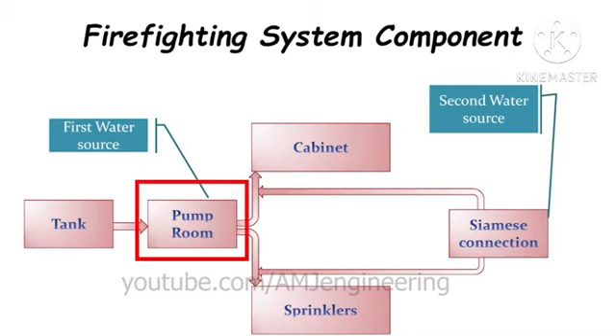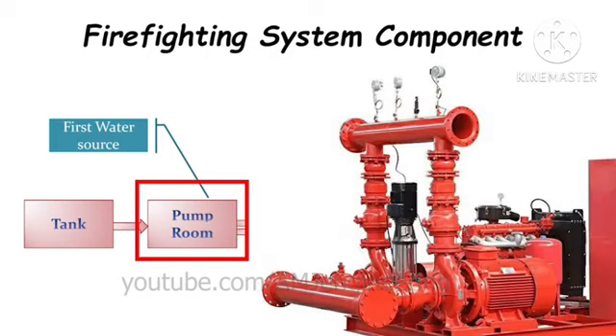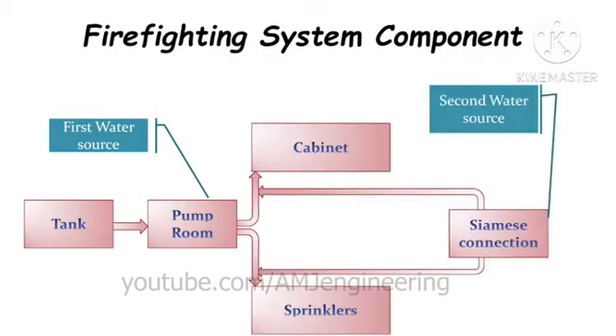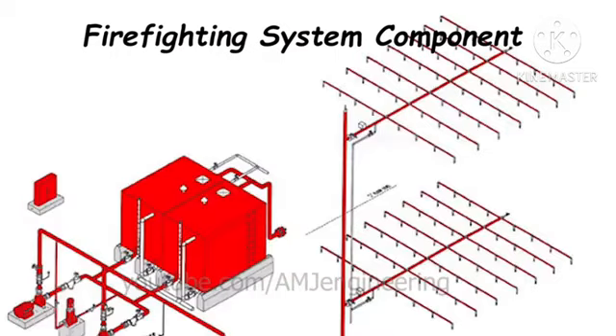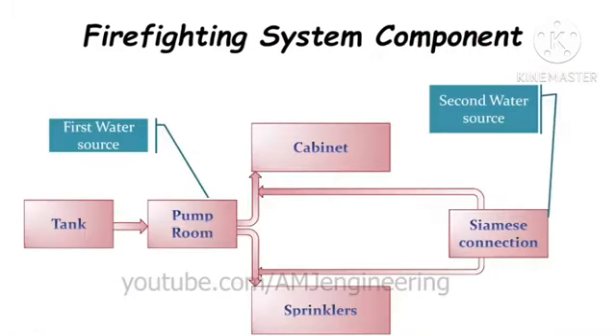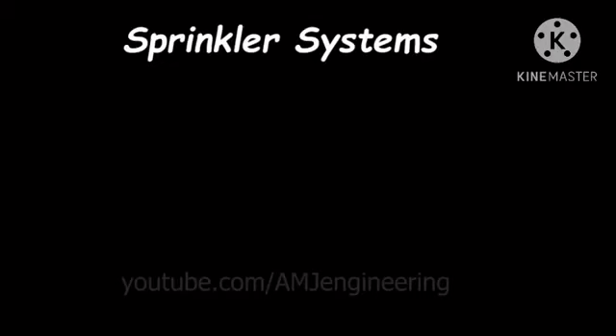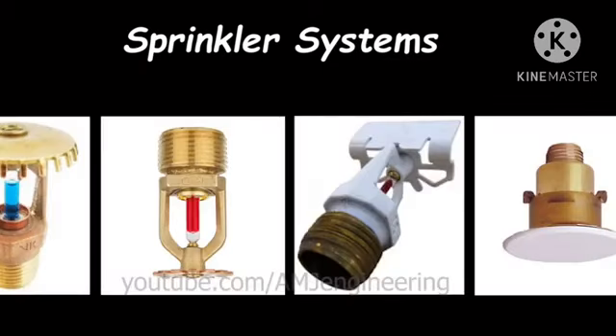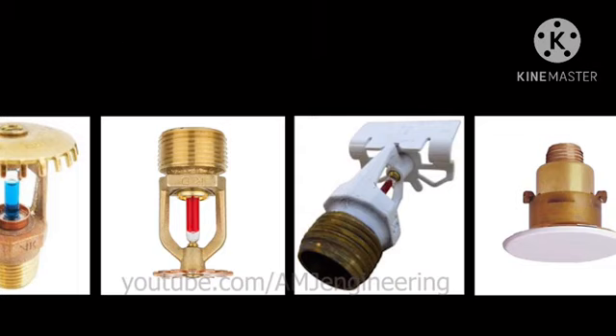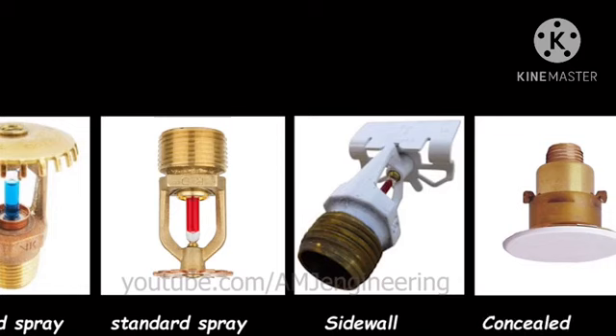A specialized pumping system. This usually includes three types of pumps: jockey pump, electric pump, and diesel pump. You can refer to my video about fire pumping system for more info. A large network of pipes ending in either hydrants or sprinklers. Nearly all buildings require both of these systems. Sprinkler systems. When it comes to the sprinkler head itself, the four most common styles of sprinklers are the standard spray upright, standard spray pendant, sidewall sprinkler, and concealed sprinkler head.